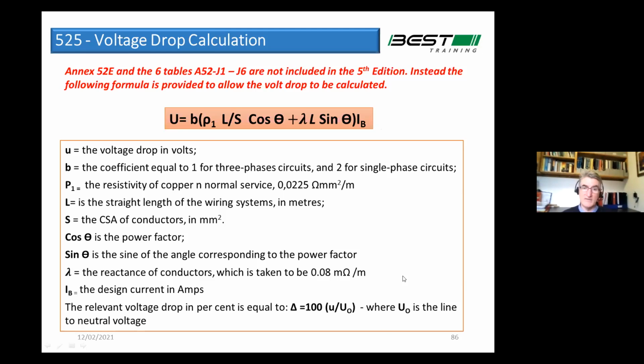Of course, if you multiply your answer back by 1.73, you'll bring it back to close to the values in the previous tables. So just to relieve anyone that's going to start worrying and say, oh God, how am I going to adapt my spreadsheet to do that? It tells you, you may calculate the voltage drop using this formula. It doesn't say you cannot use the tables anymore. Of course you can use the tables. They're IEC tables, and lots of other countries have maintained them in their wiring rules. So you can still use the old tables if you so wish. And if I was still working as a designer, that's what I'd be doing. I certainly wouldn't be using this.